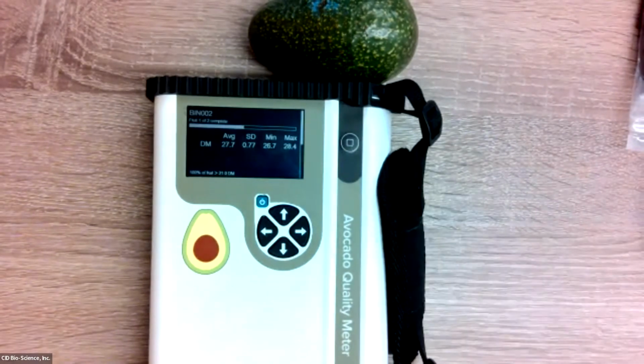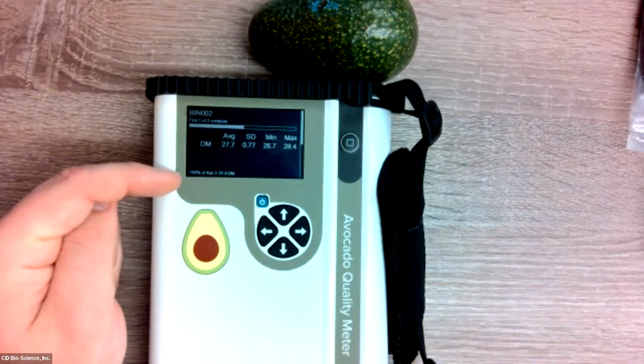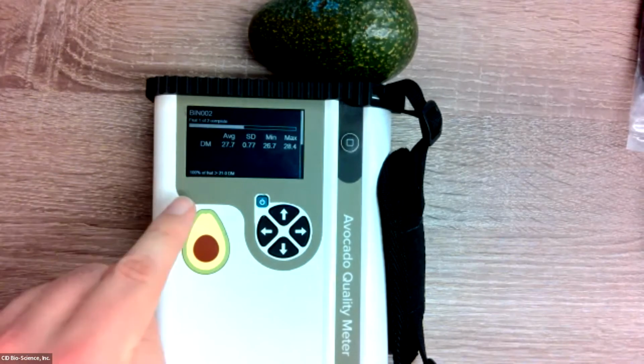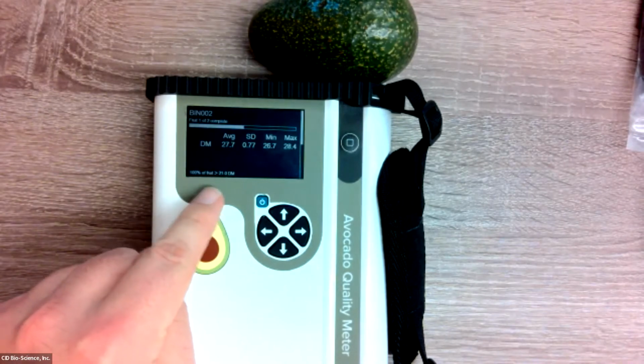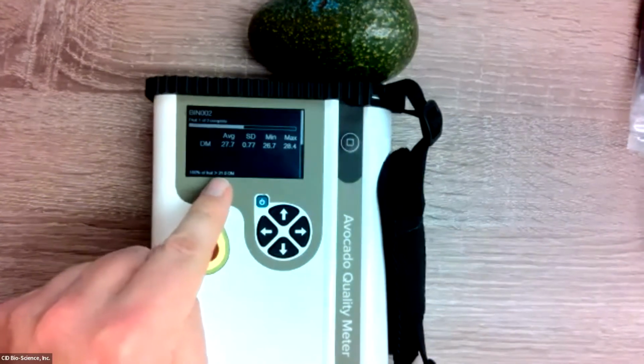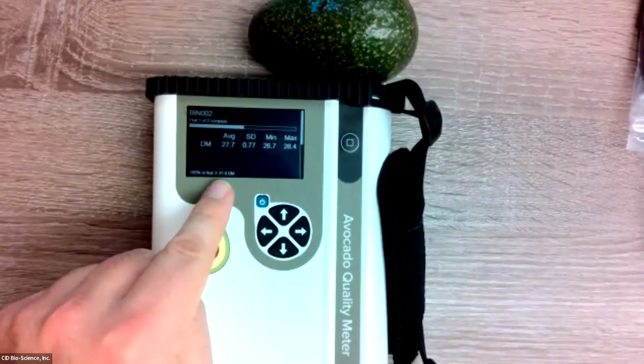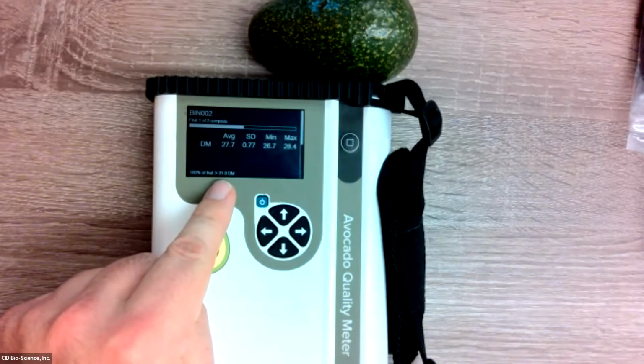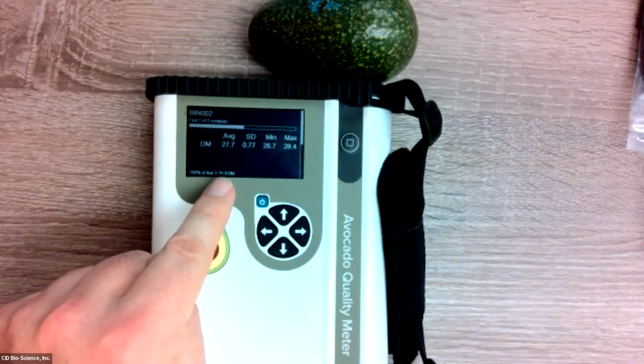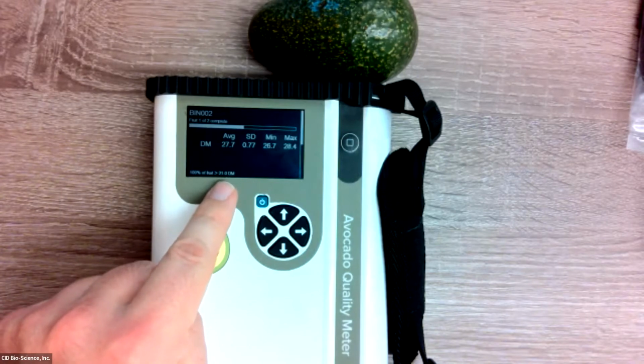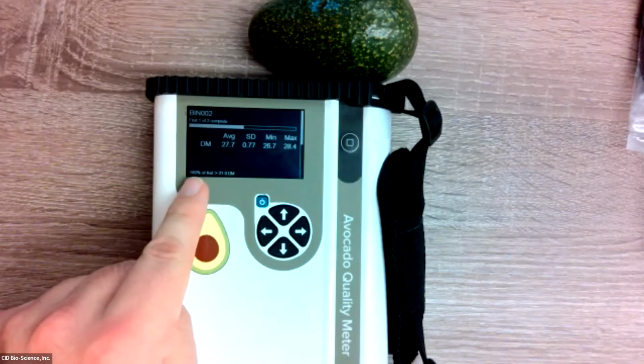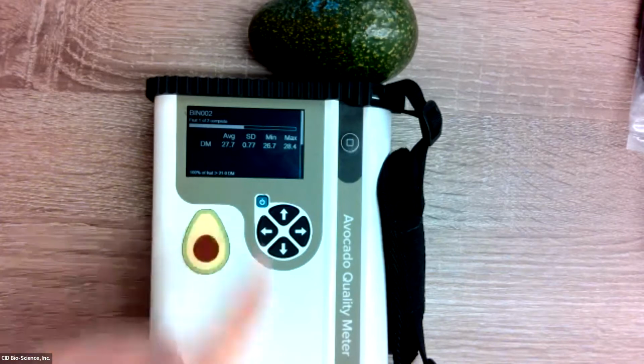There is a variety of different statistics here, including standard deviation, the minimum and maximum values within that bin. There's also a pretty neat little feature on the bottom here. This is going to let you know what percentage of fruit within your bin are greater than an established value that we call the maturity criteria. Right now it's set at 21 dry matter. You can also adjust that to be whatever number you want. So you can actually have this instrument tell you exactly how many fruit you scanned were above a certain threshold.